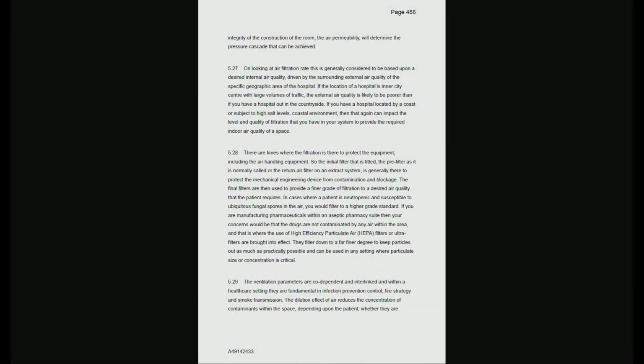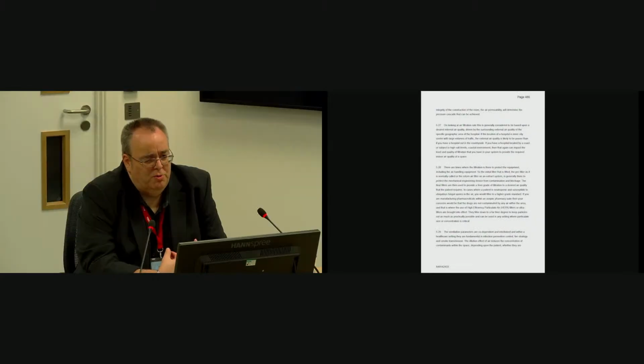I might just pick up briefly another point that you made. You may have touched on this a little earlier, page 486. At the foot of that page, you say the ventilation parameters are codependent and interlinked. Now, in the preceding section, you've been discussing the practicalities of a lot of the ventilation exercises. What do you mean by parameters are codependent and interlinked within a healthcare setting? Depending upon what you want to use the clinical space for, determines the appropriate level of ventilation required. So an operating theatre, as an example, has a far higher air change rate than a treatment room or indeed a patient bed space.